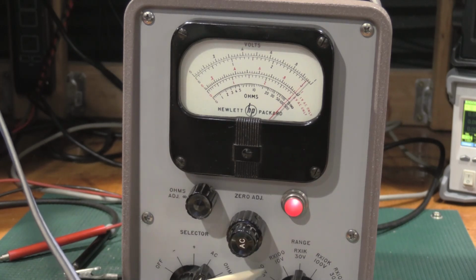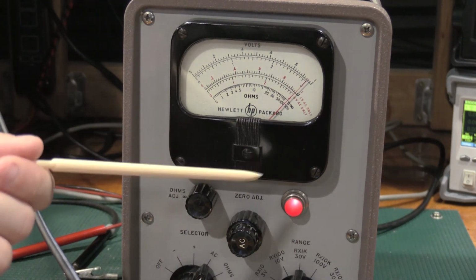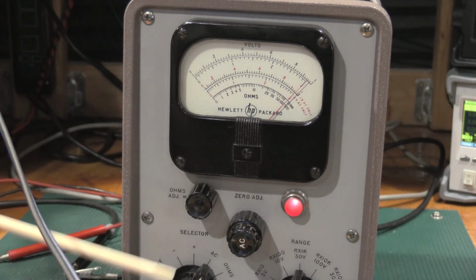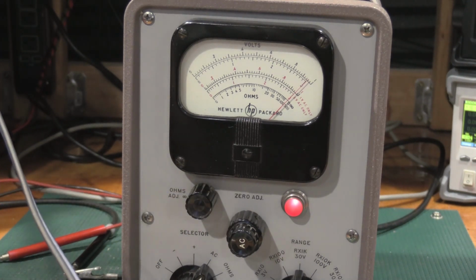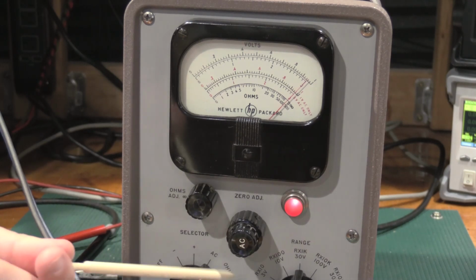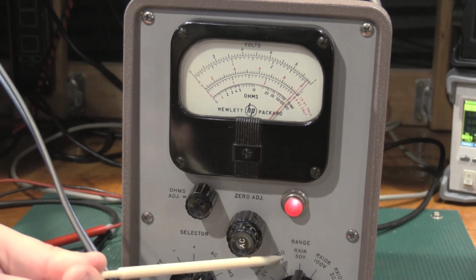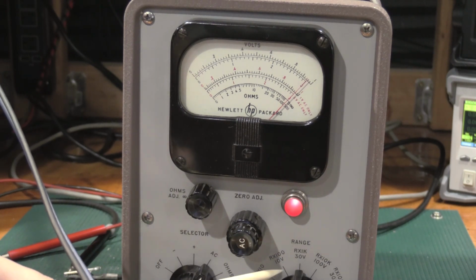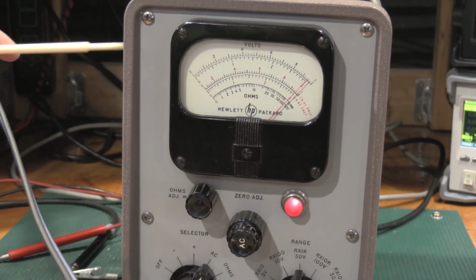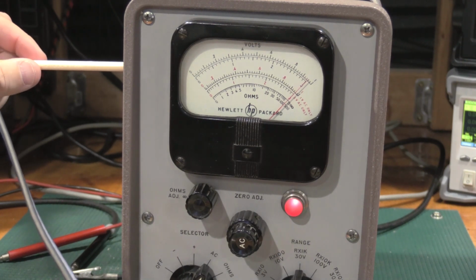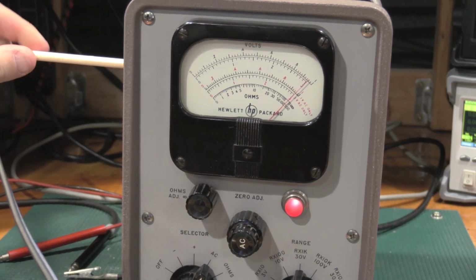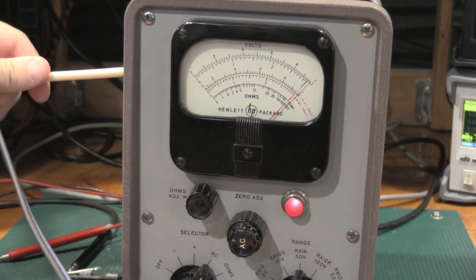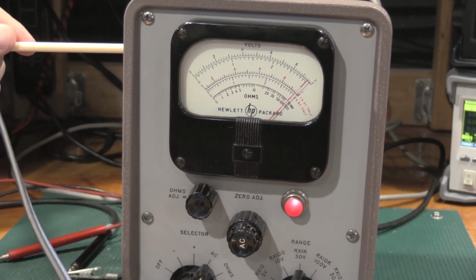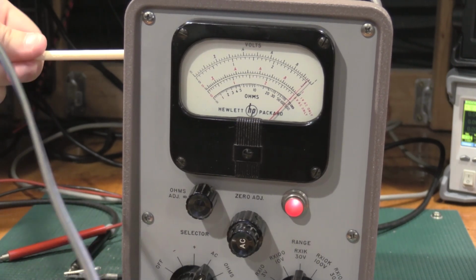So I need to redo the 3 and the 10 volt range because I just realized I forgot a step. So I'm going to redo those after I put it back in the case. I didn't set the AC 0 in between each calibration range, and I should have been doing that. The 1 volt range was fine, and the 30 volt range is fine because I did set the 0. The 10 and 3 volt ranges need to be done. The other thing that I'm going to do is for the 300 volt range and the 100 volt range, I'm going to exercise these controls.